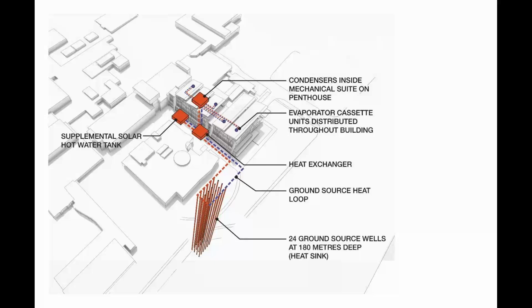We selected a ground source heat pump system, a VRF system, which we thought was very effective, because of the very superior latent heat recovery through the refrigerant loop. Because the building has very strong east and west exposure, we have differential loading. In the morning when we're overheating, we can take that heat and deposit it in other zones on the west where we need it, and vice versa when we tend to overheat in the west with the western sun—the heat moves through the system into the zones that need heating. So we have very good heat recovery and a very stable heat source for winter through the ground, and that worked out really well.